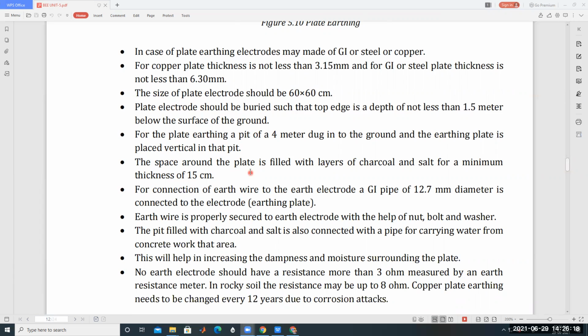For connection of the earth wire to the earth electrode, a GI pipe of 12.7 mm diameter is connected to the electrode, that is the earthing plate. The earth wire is secured to the earth electrode with the help of nut, bolt and washer. The pit is filled with charcoal and salt. It is also connected to a pipe carrying water from the concrete work in that area.